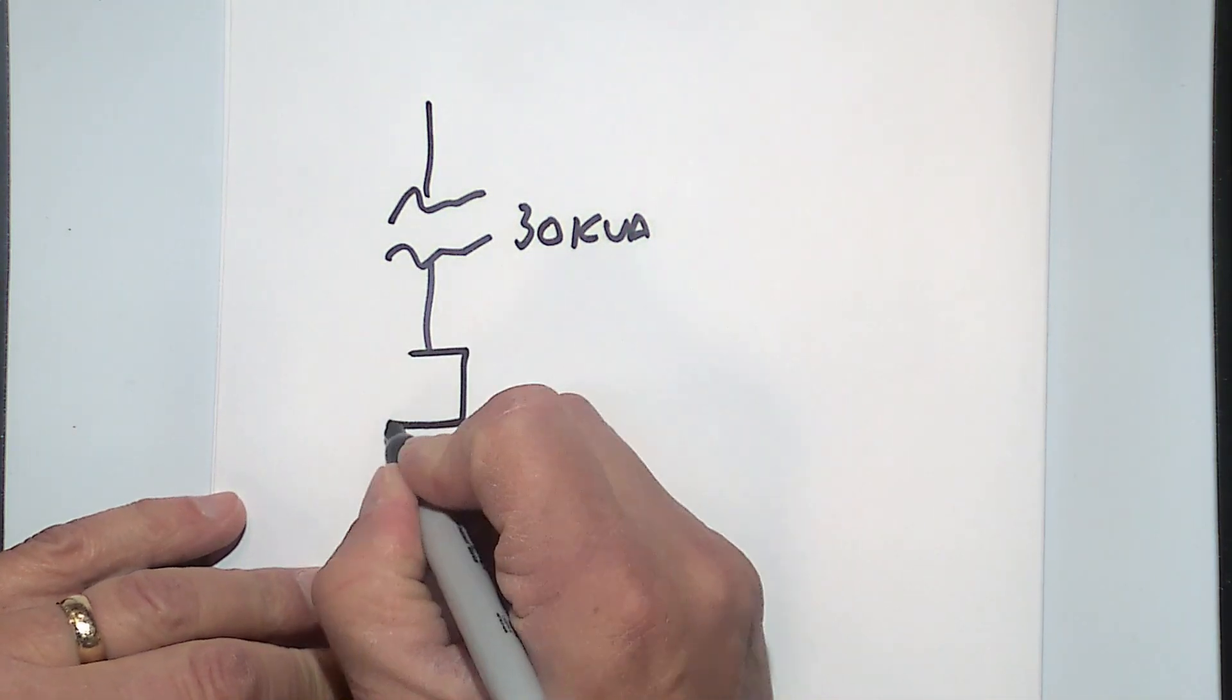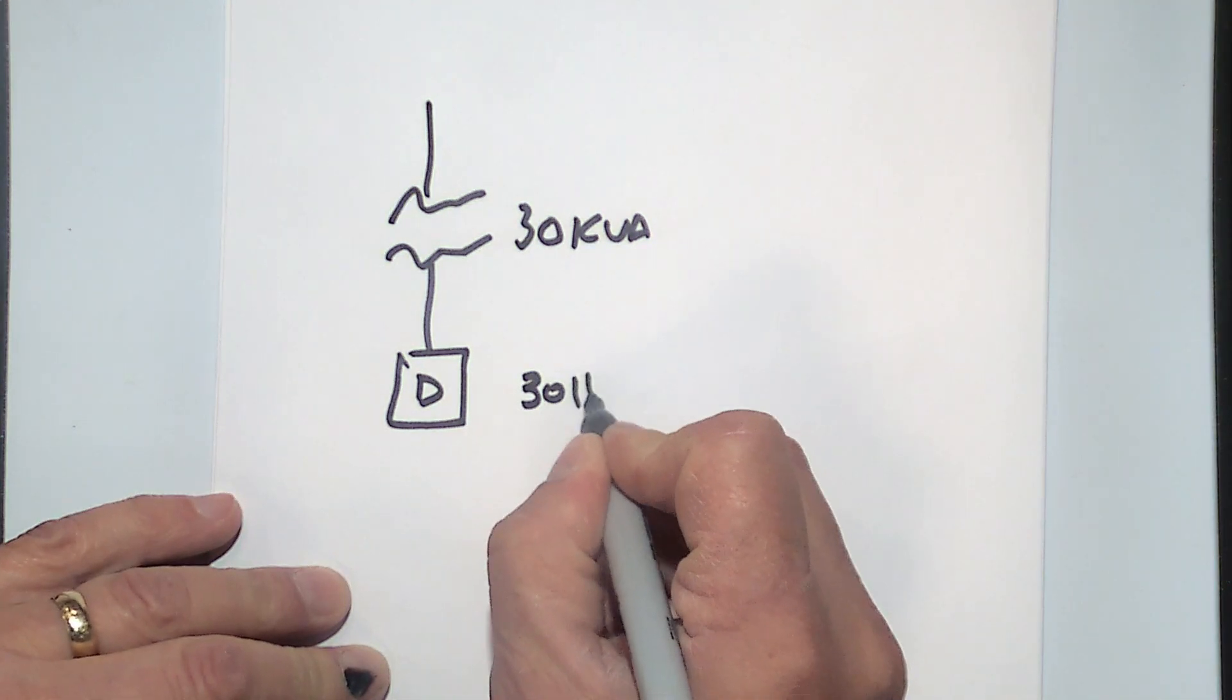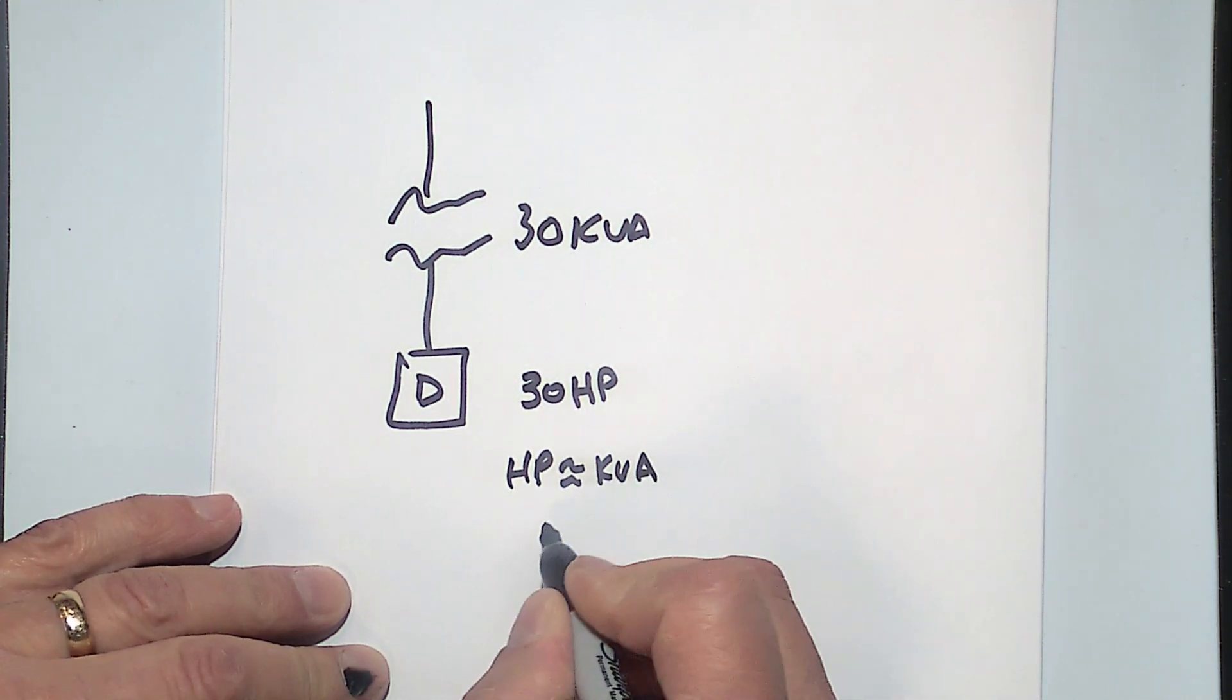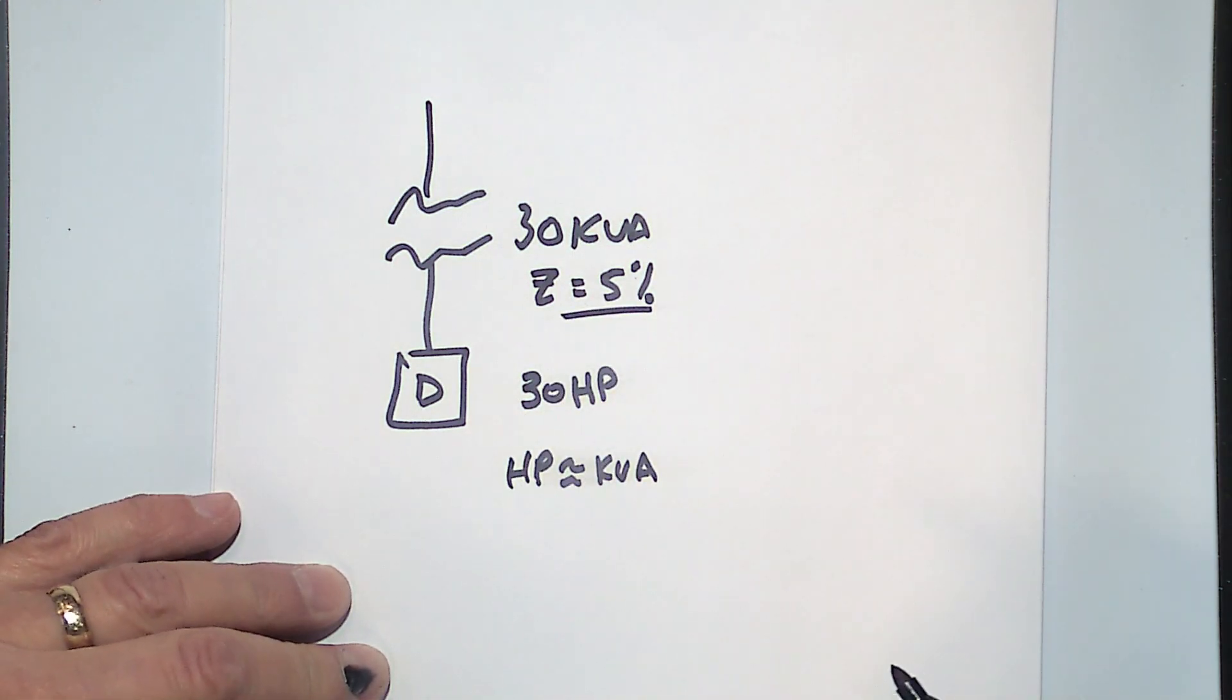So if I have a transformer, let's say it's a 30 kVA transformer, and I have a drive. And let's say that drive is 30 horsepower. Well, horsepower is about equivalent to kVA. So if I have 30 horsepower, I have about 30 kVA. Now, if this impedance or Z is 5%, then I effectively have about a 5% line reactor because most of that impedance is inductance.